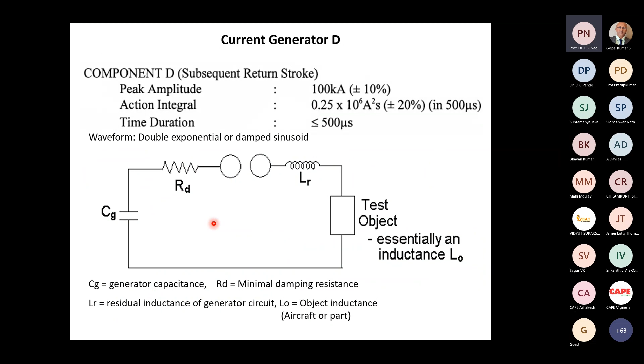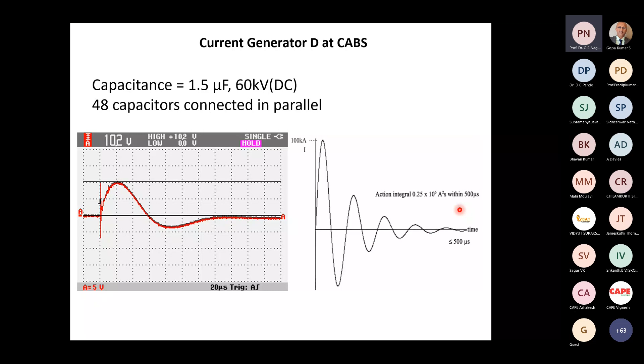Now current generator D is very similar to current generator A, but the specifications are somewhat different. Here we have typically 1.5 microfarad, 48 capacitors in parallel. This is the oscillogram, and this is also the plotted wave shape. Current is 100 kiloamperes, and the duration is such that the action integral is 0.25 times 10 to the 6 amperes squared per second.